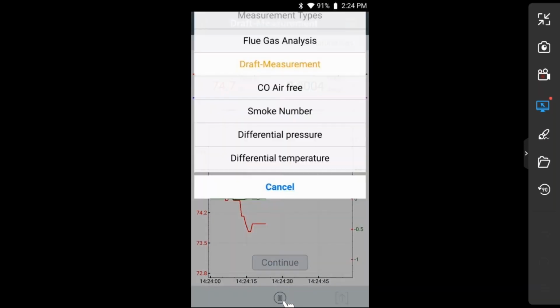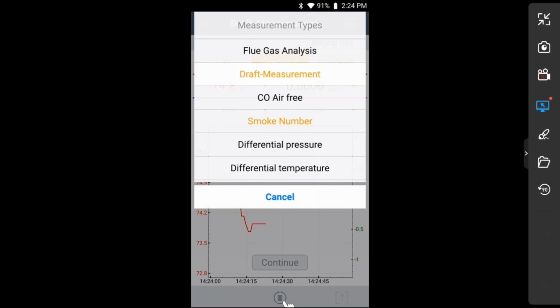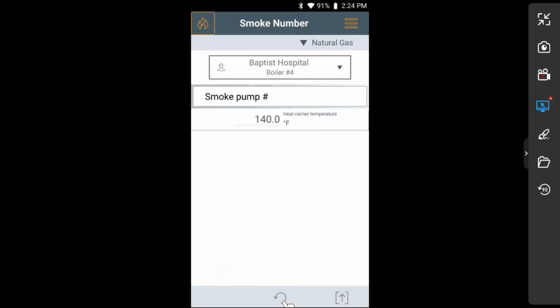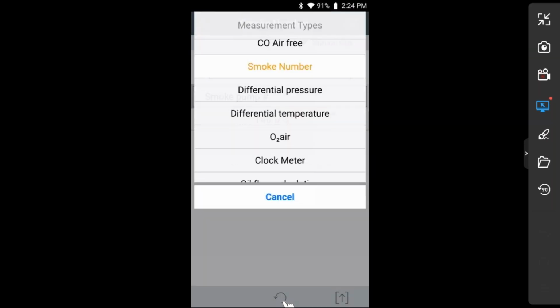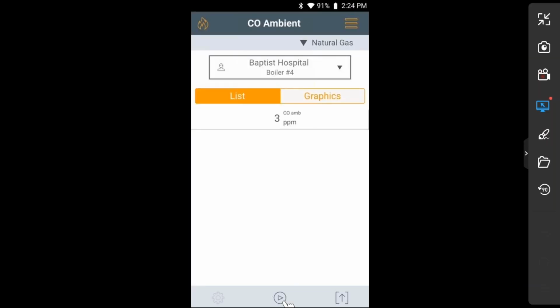The other measurement that you're going to be using quite a bit, I believe, or you could, is a reading called CO ambient. If you're doing any type of residential or commercial boiler tuning, you can also measure ambient air. And I just put it into the ambient air mode.